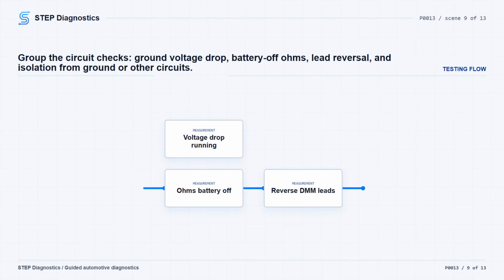Expect less than 2 ohms for most small diameter 18 gauge and smaller wires, and expect less than 2 ohms of resistance for most wiring harness circuits. Also remember that a standard DMM ohm meter's low resistance resolution, approximately 0.1 ohm, limits its accurate use to circuits carrying less than approximately 5 amperes.